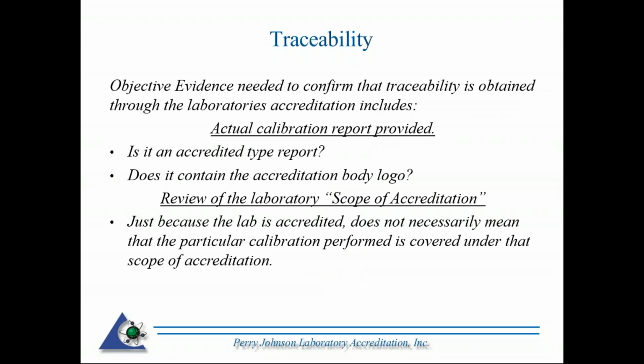Just a little tidbit here. Even if the laboratory is accredited, if you're using it as a source, you want to assure that you're getting an accredited type report, a report that's intended to fall under their scope of accreditation. You have the data, and you also have the uncertainty. By definition, the results are not traceable without the uncertainty. If the report contains the accreditation body logo, then by all means it is intended to fall under the lab's scope of accreditation. Again, review the laboratory's scope of accreditation. A lab can be accredited, but that does not necessarily mean the particular calibration that was performed is covered under that scope. It's just a little extra legwork to assure you're getting traceable measurements, even though the organization is accredited, the calibration is covered under their scope, and you're getting the accredited report.